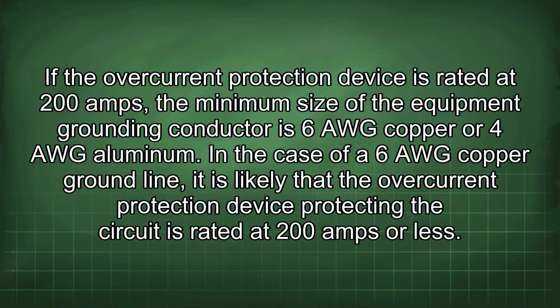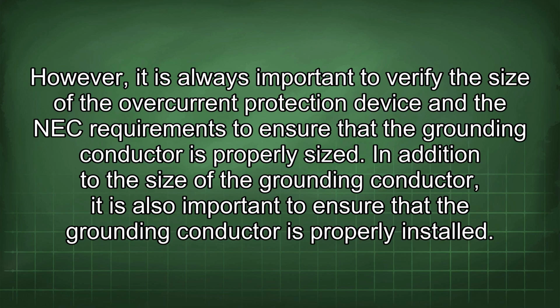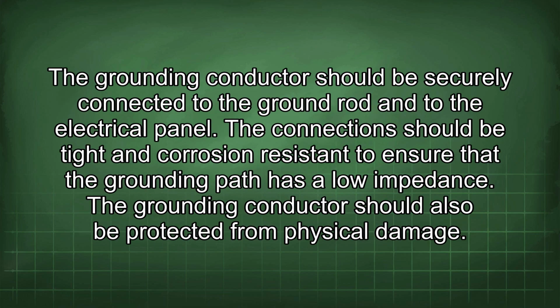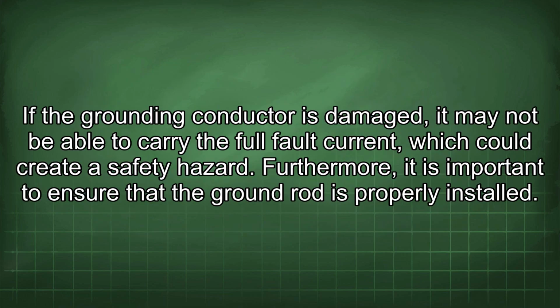In the case of a 6 AWG copper ground line, it is likely that the overcurrent protection device protecting the circuit is rated at 200 amps or less. However, it is always important to verify the size of the overcurrent protection device and the NEC requirements to ensure that the grounding conductor is properly sized. In addition to the size of the grounding conductor, it is also important to ensure that it is properly installed. The grounding conductor should be securely connected to the ground rod and to the electrical panel. The connection should be tight and corrosion resistant to ensure that the grounding path has a low impedance. The grounding conductor should also be protected from physical damage.